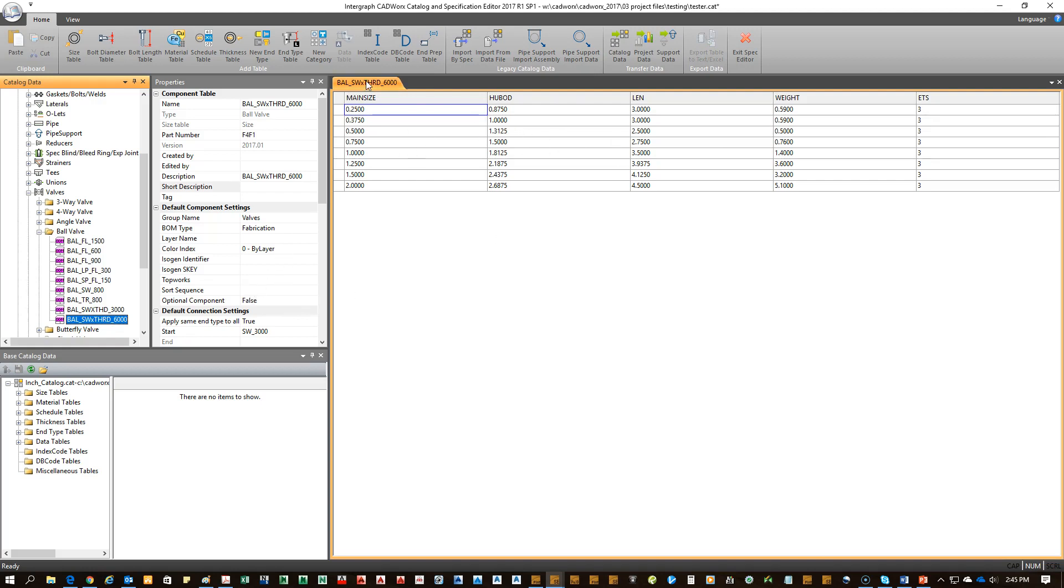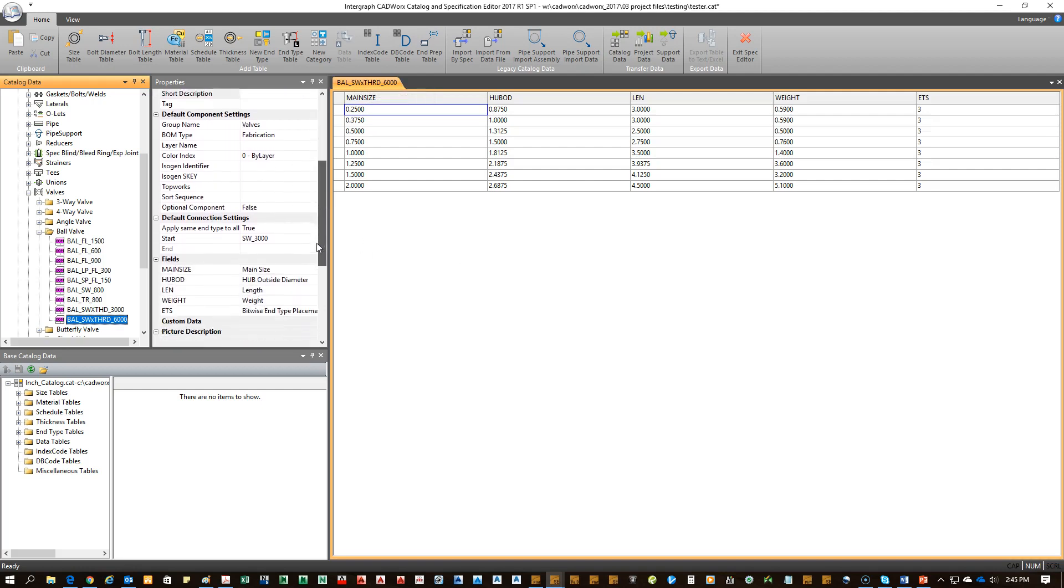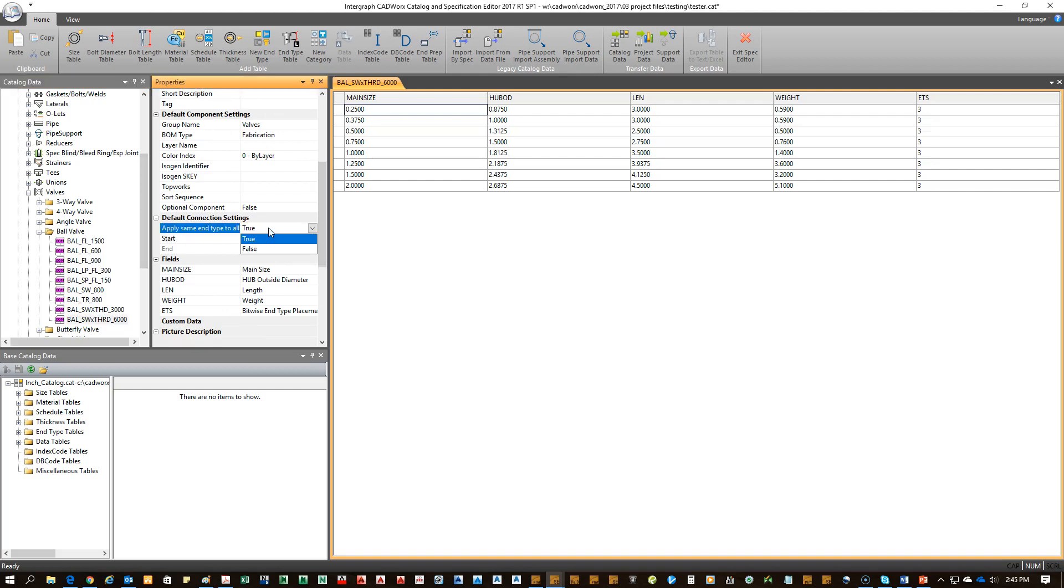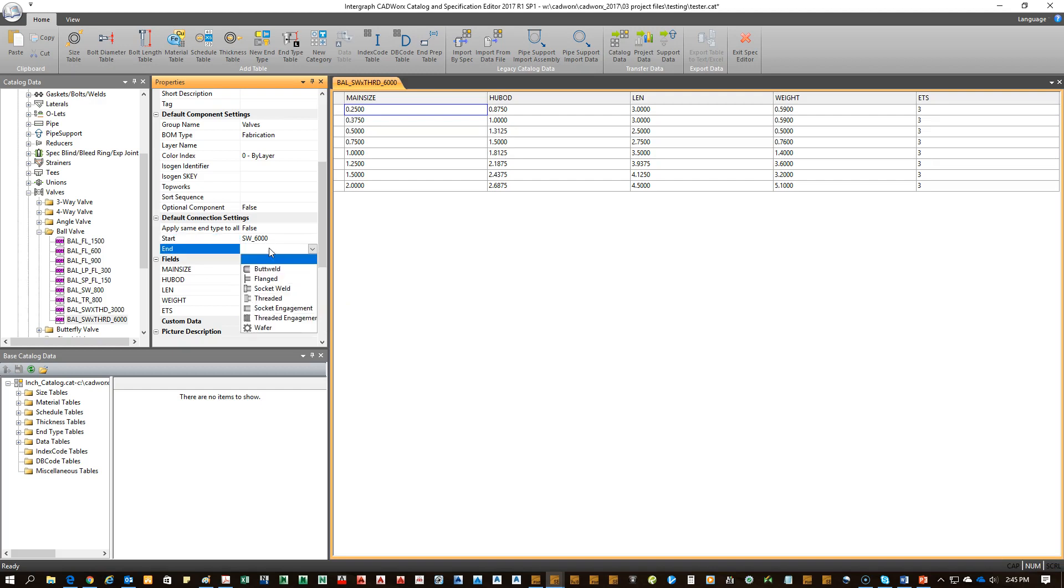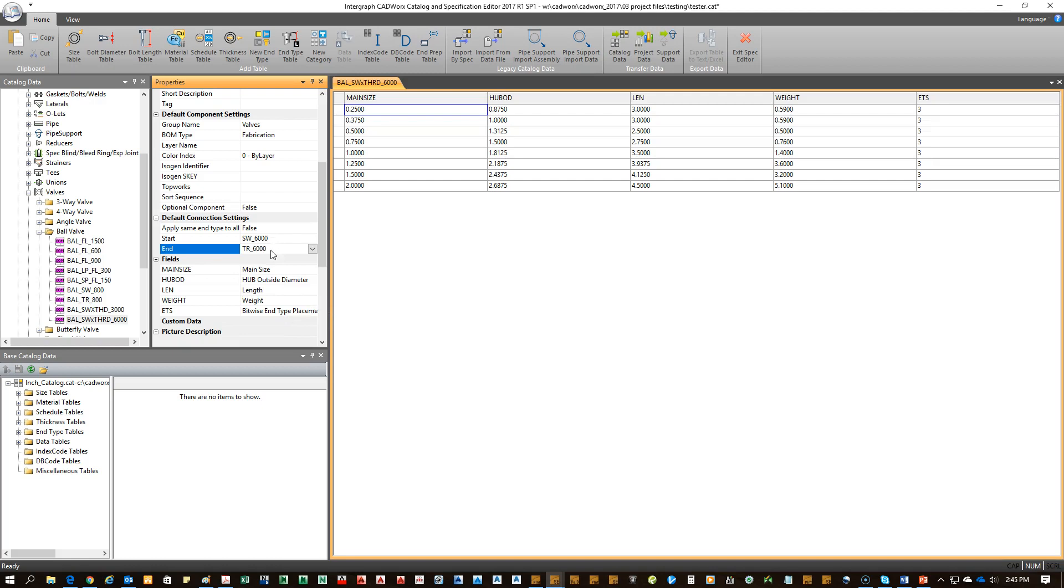To make it so that the end conditions are unique, you'll come down to the summary, the properties pane, and you're going to click on apply same end types to all ends. You're going to say false since they're going to be different. Come over here. I'm switching my first endpoint to socket weld 6,000, threaded 6,000. So they're both now socket weld by threaded 6,000 pound each.